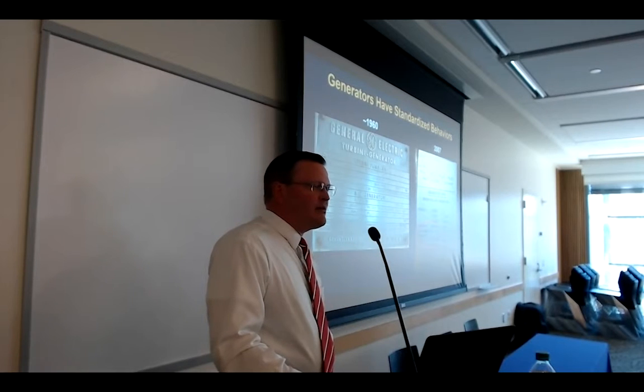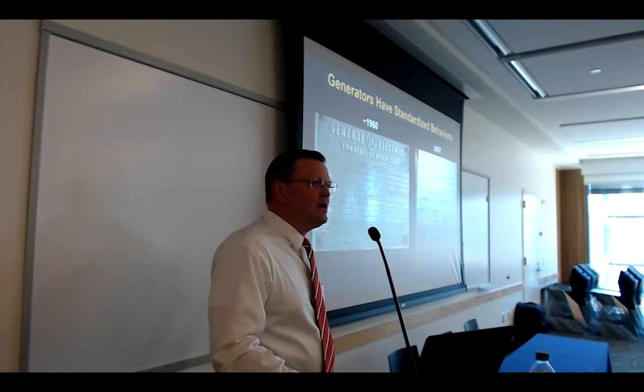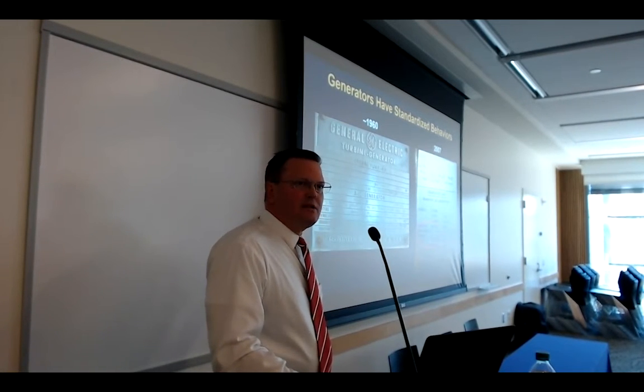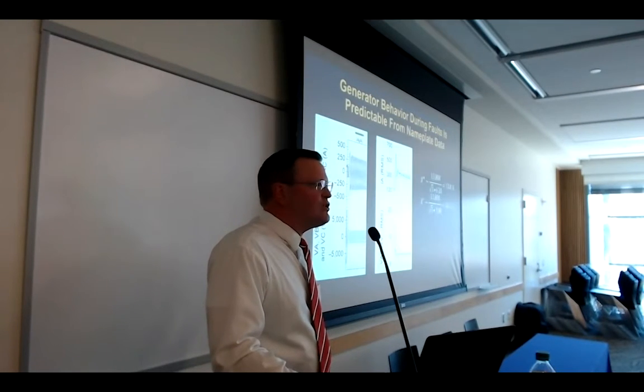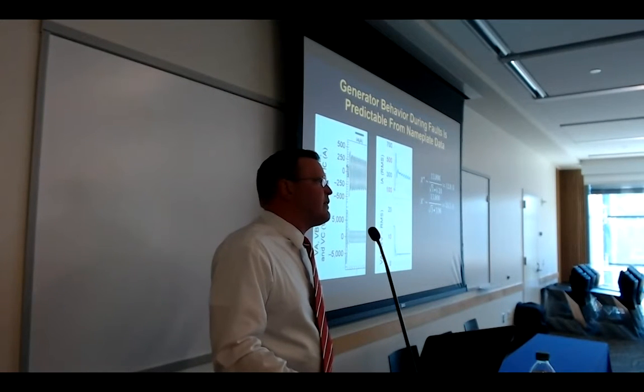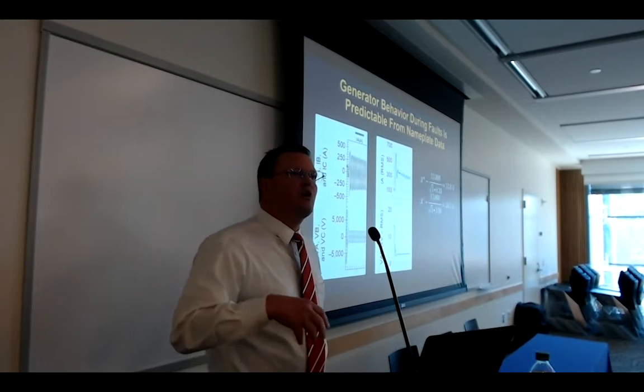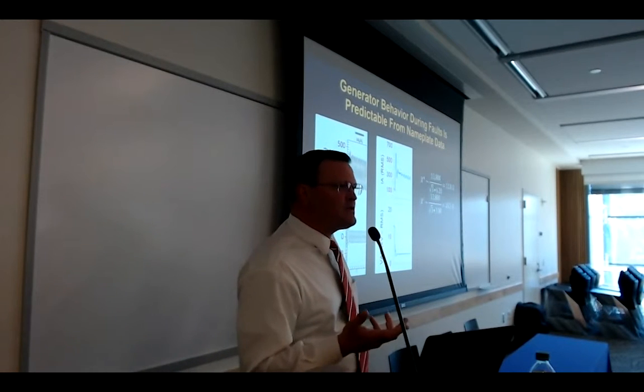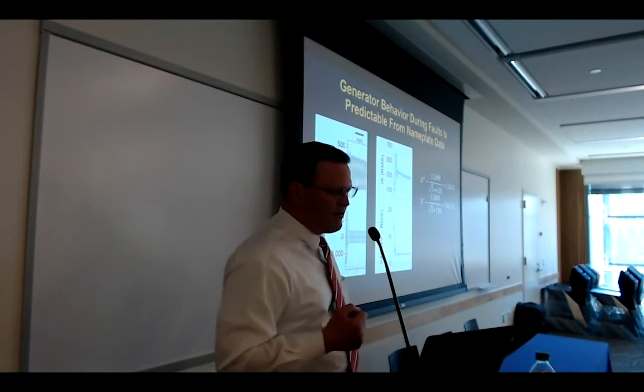Here, embedded on the nameplate on the right, is the subtransient and transient reactance. Those numbers are used to calculate the fault capacity - how much current, how much juice this generator is going to provide during a fault event.